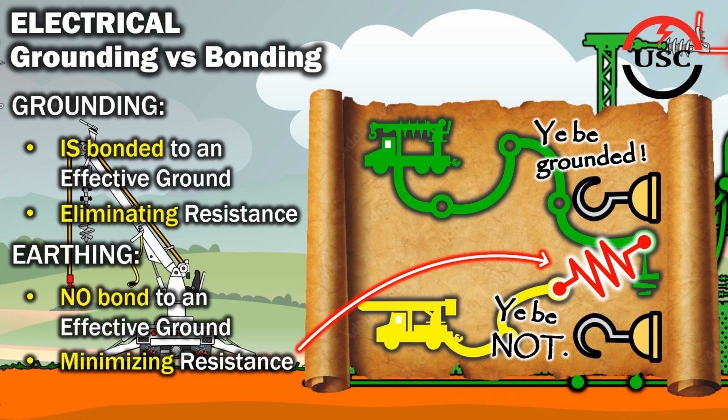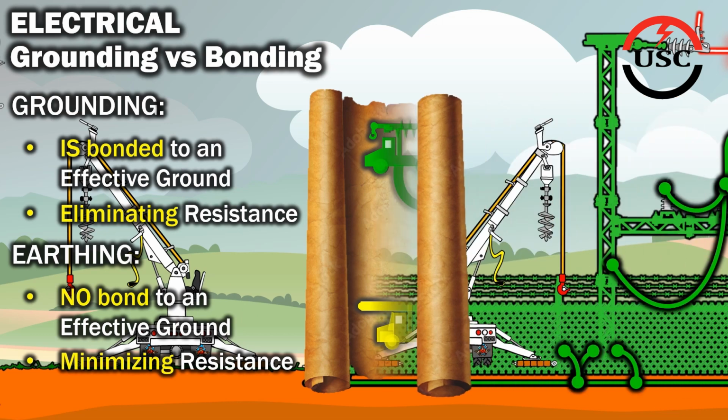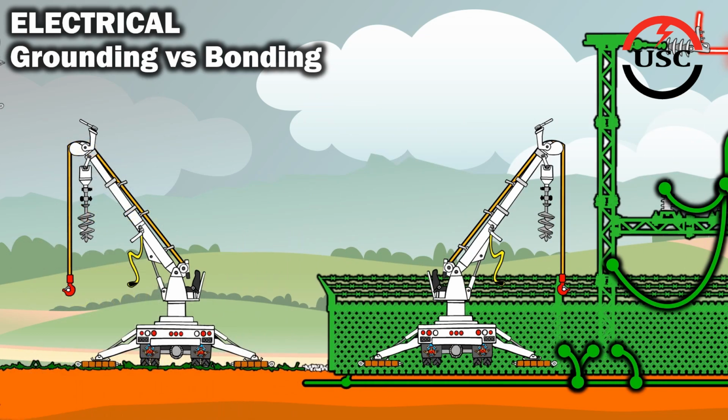Cases can include when relying on the pole ground, a temporary ground rod, and in some cases, maybe the overhead static wire when it is being used solely for lightning protection, which we'll discuss here in a minute. Keep in mind, the key of earthing is the absence of the effective ground, because without this effective ground, there is no 0-volt energy reference with regards to the system.